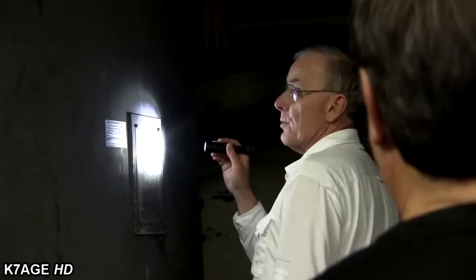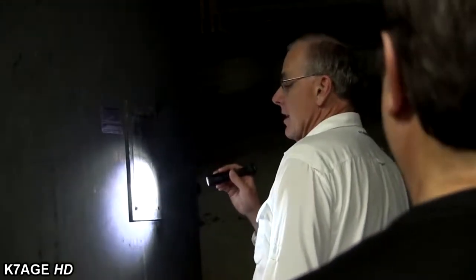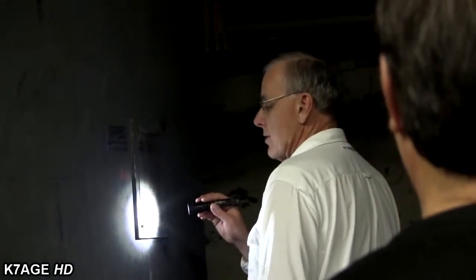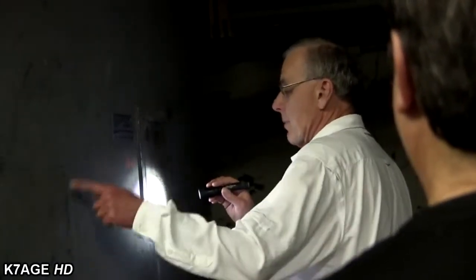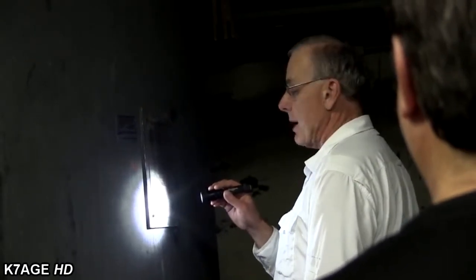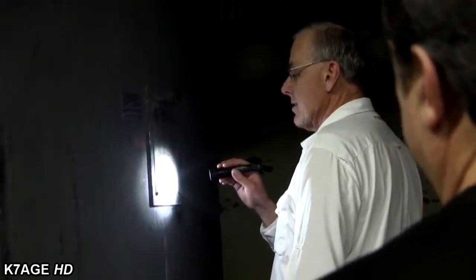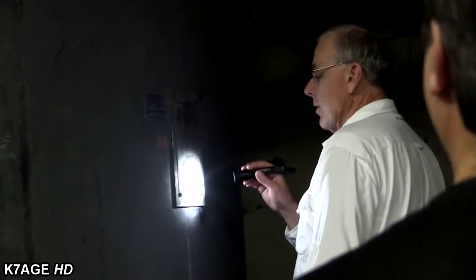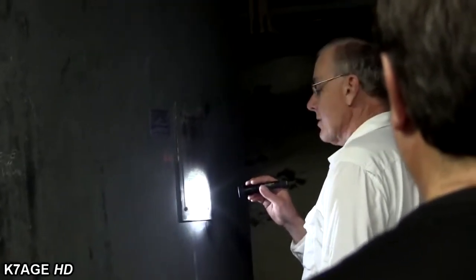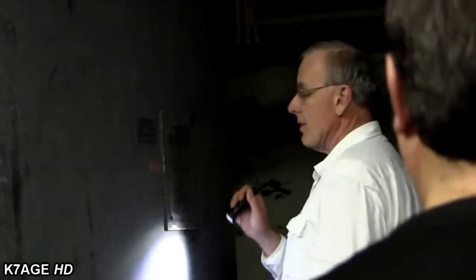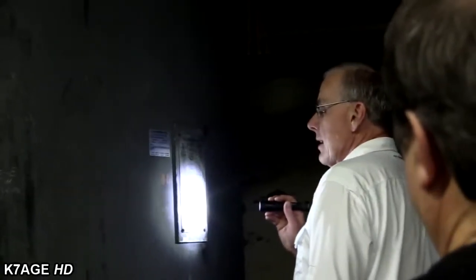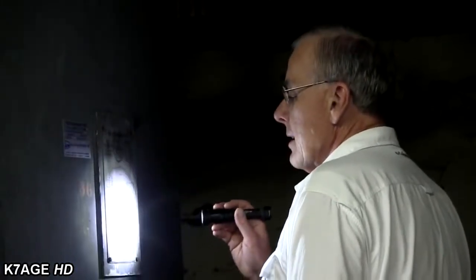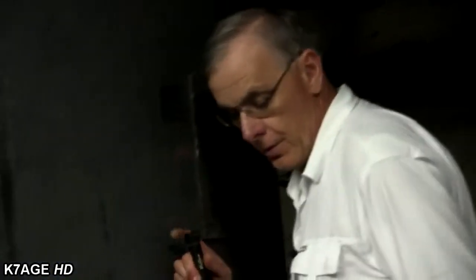It has 725 gallons of oil in it. So the approximate weight of the magnetics of this one by itself is 27,000 pounds of steel, iron in it. The case is 3,250 pounds. The oil is 5,460 pounds. Its total weight is 35,700 pounds for this, okay? The high voltage input was rated up to 14,400 volts. So this was one of two modulation transformers.